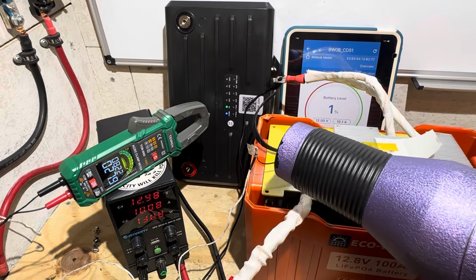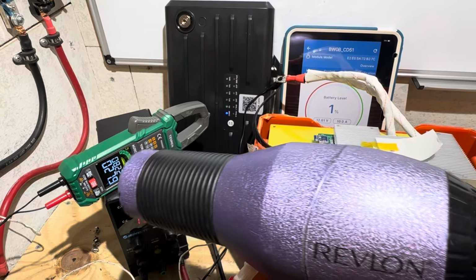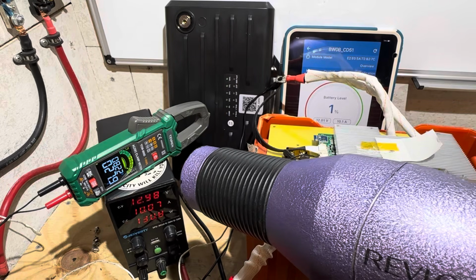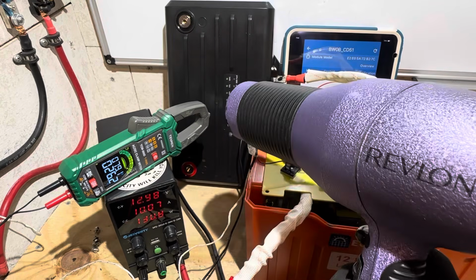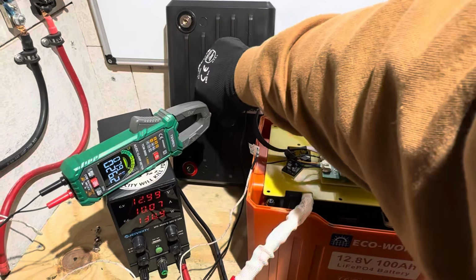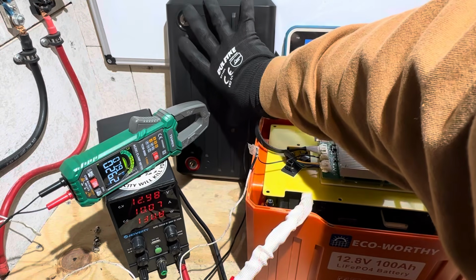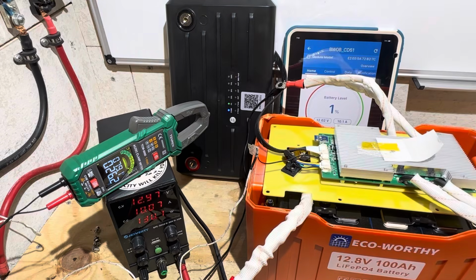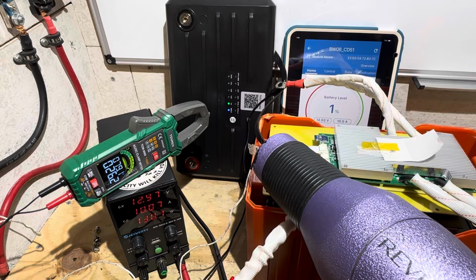I'll do the high temp check first. I'll apply heat to the sensor, and you'll see the temperature climb. Whenever the over-temperature protection triggers, you'll see the current drop, and we should get an indicator. Let me turn the display back on, it times out after a couple minutes. There we go, got the display back on. Now we're set, here we go.